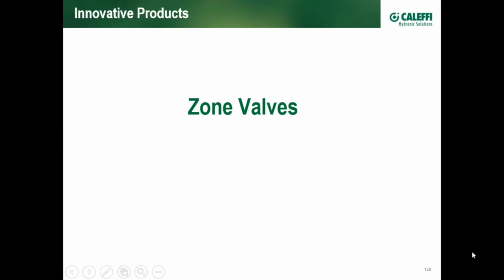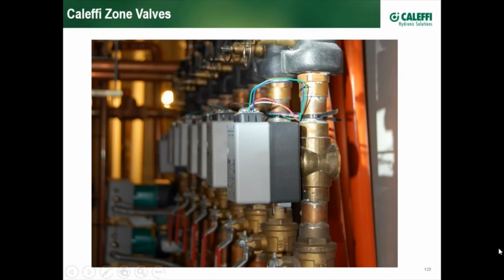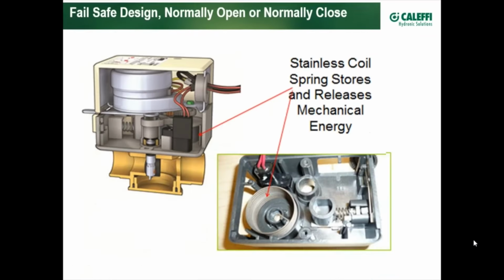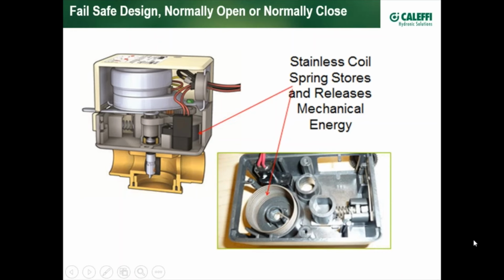Zone valves. Caleffi makes a lot of them, approaching a couple of million sold in North America to date, largely because of the reliability of the valve. I could talk for an hour about the different things we do on reliability, but here's an example. Each one of our coil springs is calibrated to the precise torque needed to deliver the close-off pressure that the valve is rated for. For example, 75 PSI or 50 PSI.